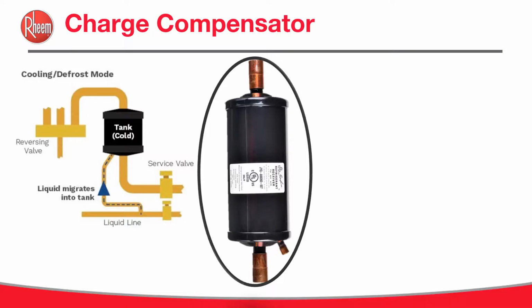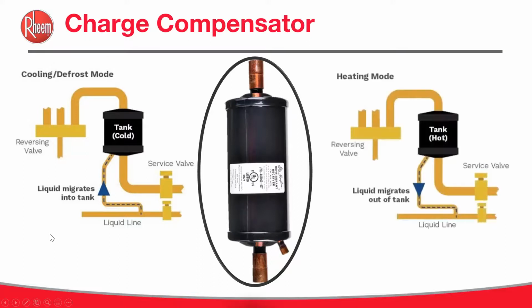So what happens when the reversing valve is connected to the liquid line via a T? When in cooling mode, the tank is cold, so extra refrigerant will migrate into the tank and be stored. In heating mode, the tank is hot, right? So on this system, the tank is now hot, and the extra refrigerant that was stored in that tank migrates back into the system, and we don't keep anything there.